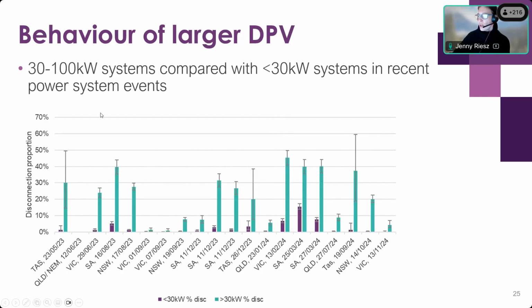There's also a whole suite of issues we're still grappling with. This chart shows different power system incidents that happened on different dates and in different parts of our grid, and the proportion of distributed PV that disconnected in those events. The purple bars are the small systems, less than 30 kilowatt rooftop PV systems, and the green bars are the larger ones, in the range of 30 to 100 kilowatts.